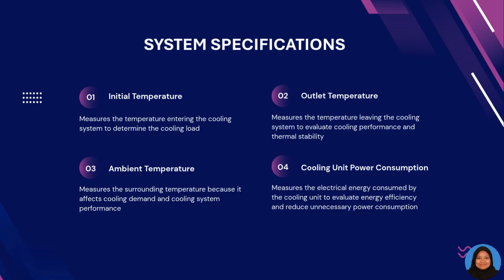Next is the system specification. First, inlet temperature, to measure the temperature entering the cooling system to determine the cooling load. Second, outlet temperature, to measure the temperature leaving the cooling system to evaluate cooling performance and thermal stability. Third, ambient temperature, to measure the surrounding temperature because it affects cooling demand and cooling system performance. And lastly, cooling unit power consumption, to measure the electrical energy consumed by the cooling unit to evaluate energy efficiency and reduce unnecessary power consumption.